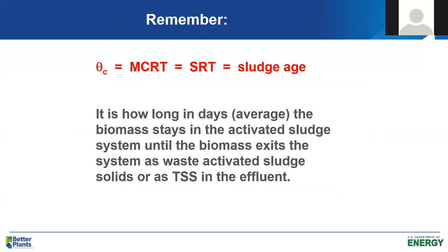As I mentioned in the discussion about the biomass, sludge age is extremely important in activated sludge. It controls the process. So when we design an activated sludge process, sludge age is a key design parameter. When you're operating an activated sludge process, sludge age is a key operating parameter. In my mathematical equations, I usually use the parameter theta sub C to represent sludge age. We said the other day it's also called MCRT, mean cell residence time, or solids retention time, SRT, but it's like saying soft drink, soda pop, Coke, Pepsi. Basically, we're saying the same thing.